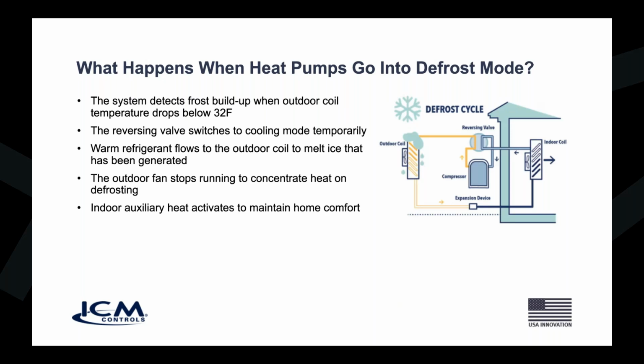Now that's basically how the heat pump works and how the defrost board works. So obviously you can see that for heat pumps, we need this defrost control board. And we're seeing a lot of these heat pumps around now, not just in warm climates, all over. So all heat pumps will have to have some form of defrost control, and that's why we made the universal defrost control.